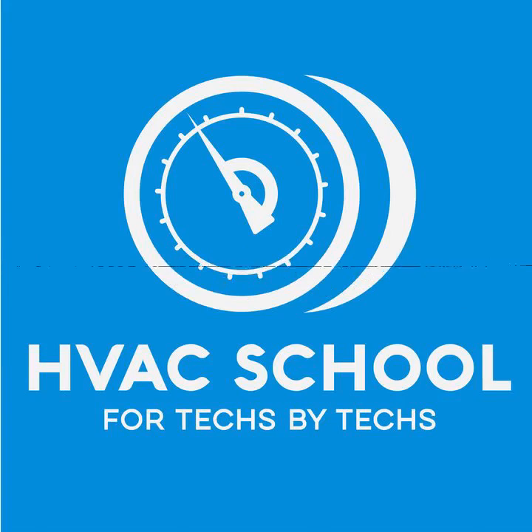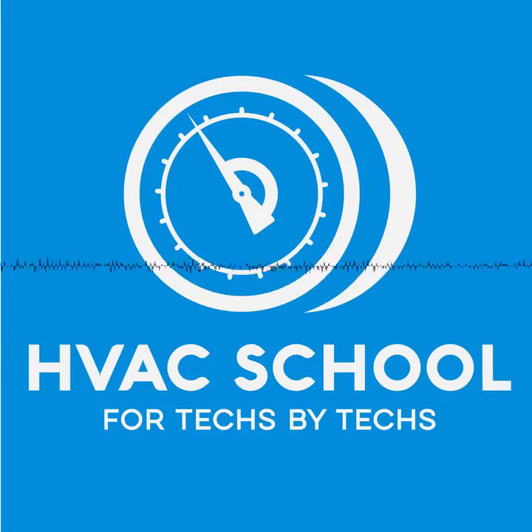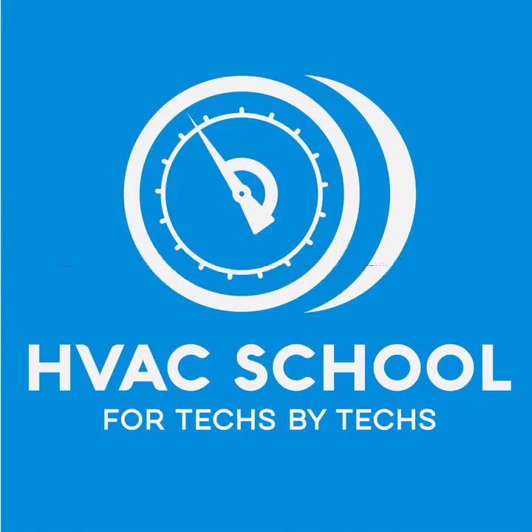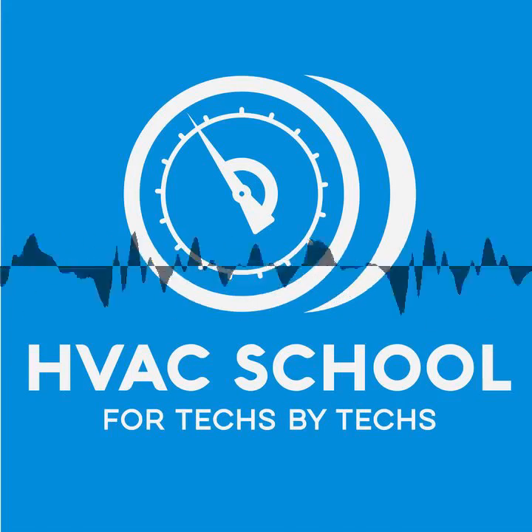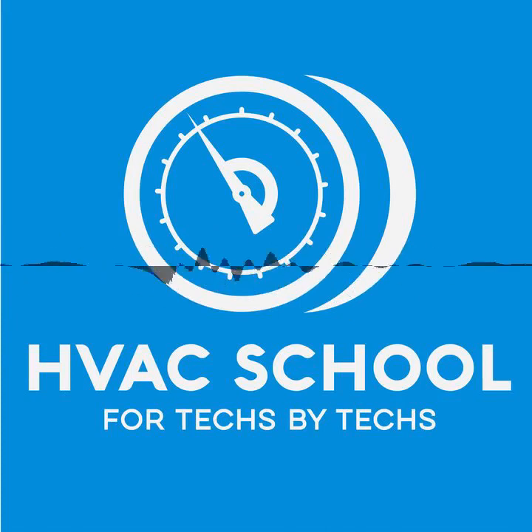A steam heating primer. If you ask a dozen people what the proper operating pressure for a steam system is, you'll probably get a dozen different answers. Most folks just follow what they were taught without giving much thought to the results. Most steam systems run at ridiculously high pressures. As early as 1900, residential boiler manufacturers decided that no house heating steam system should operate at a pressure higher than 2 psi. They could make this statement because it's latent heat, not steam pressure, that does the actual heating work in a residential system. Latent heat is the energy we put into water to get it to change state from liquid to gas. In the early 1800s, an Englishman named Thomas Tredgold coined the term British Thermal Unit. He defined the BTU as the quantity of heat needed to raise the temperature of one cubic foot of water one degree Fahrenheit. After he died, folks changed the cubic foot to a pound, which is about a pint of water — they could do that because Mr. Treadgold was just making it up.